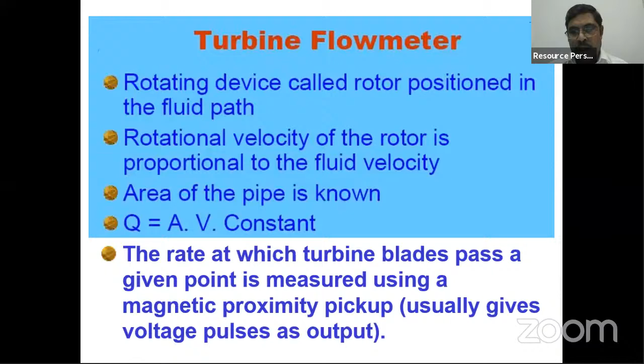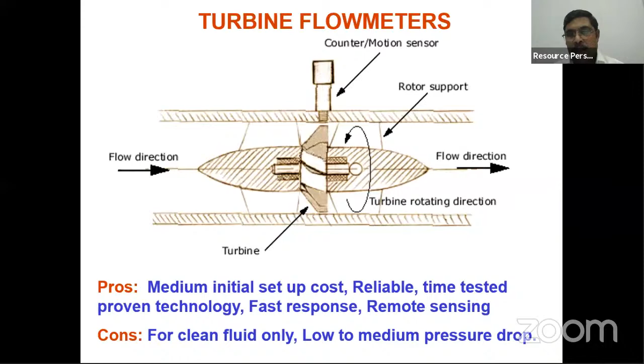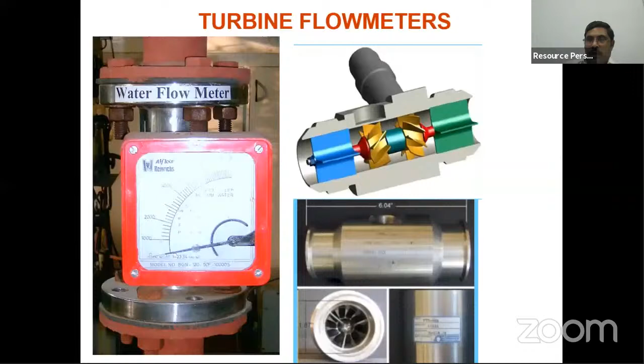And electronically also you can measure. There will be a proximity sensor. The sensor will be kept outside the tube. Basically, the sensor will sense the number of rotations of the turbine. So from the number of rotations of the turbine, you can get the flow rate. This can be used for both steady and unsteady flow, and flow meters are available for both liquid and gas. Okay, so as I already mentioned, this can be used anywhere between 0.1, maybe 0.5 inch diameter up to large sizes, like 10 inch or 20 inch diameter. These are also available.